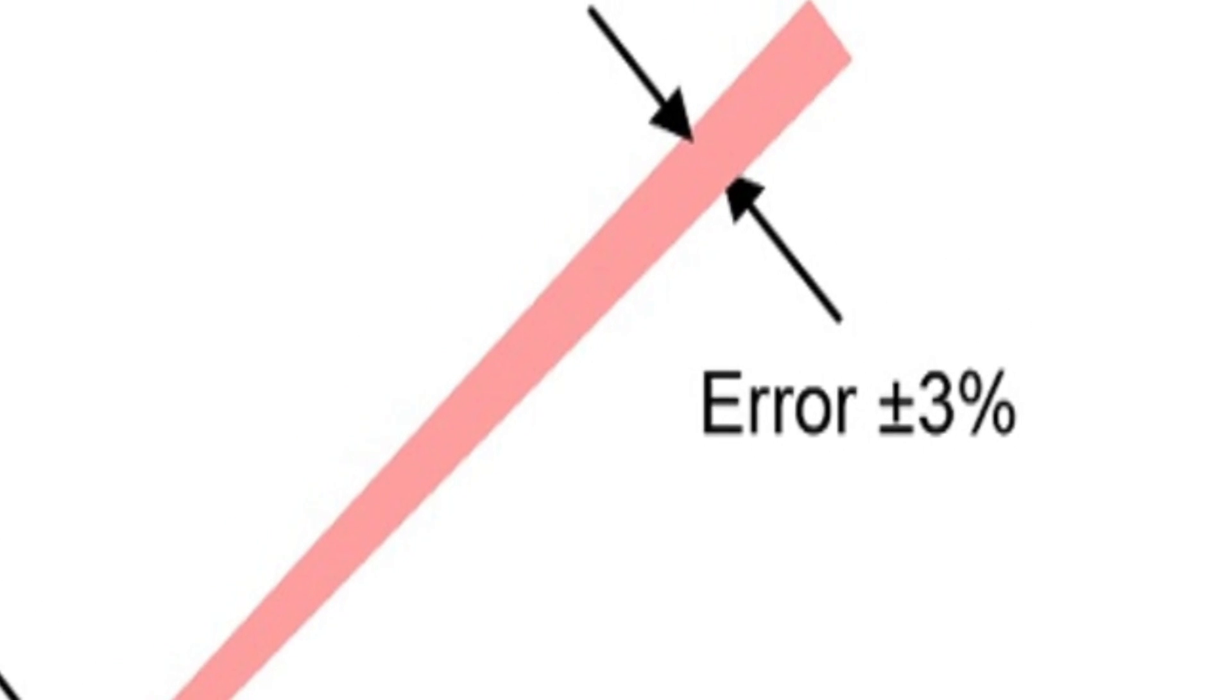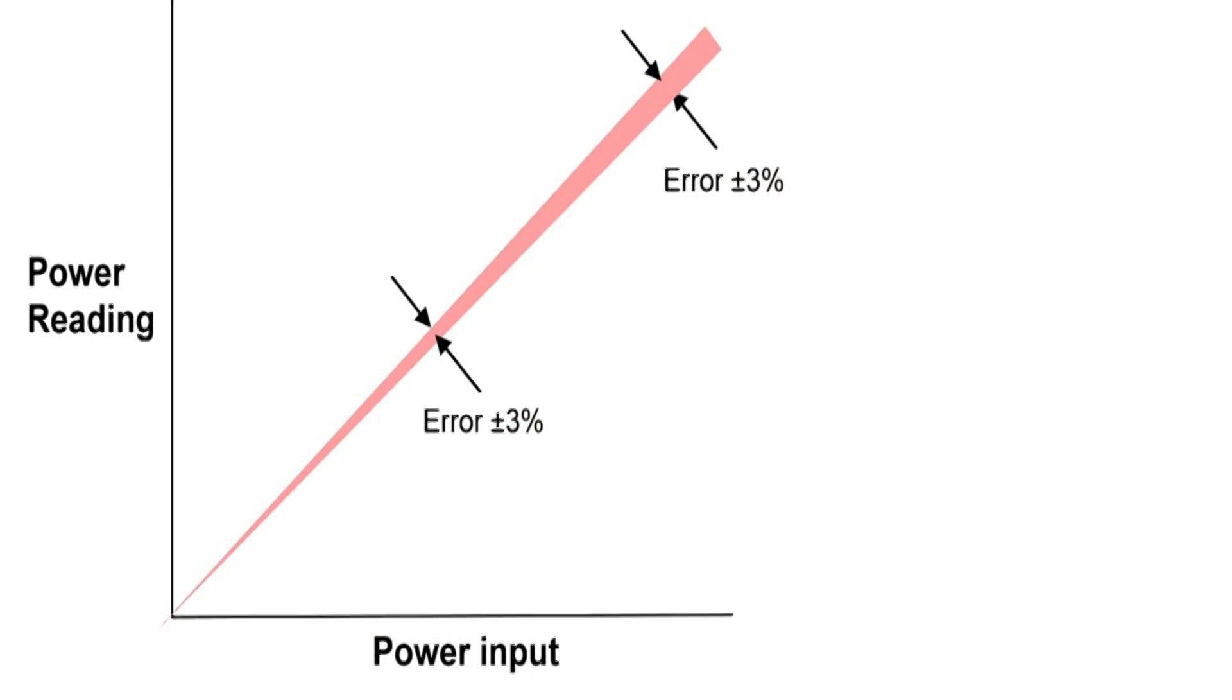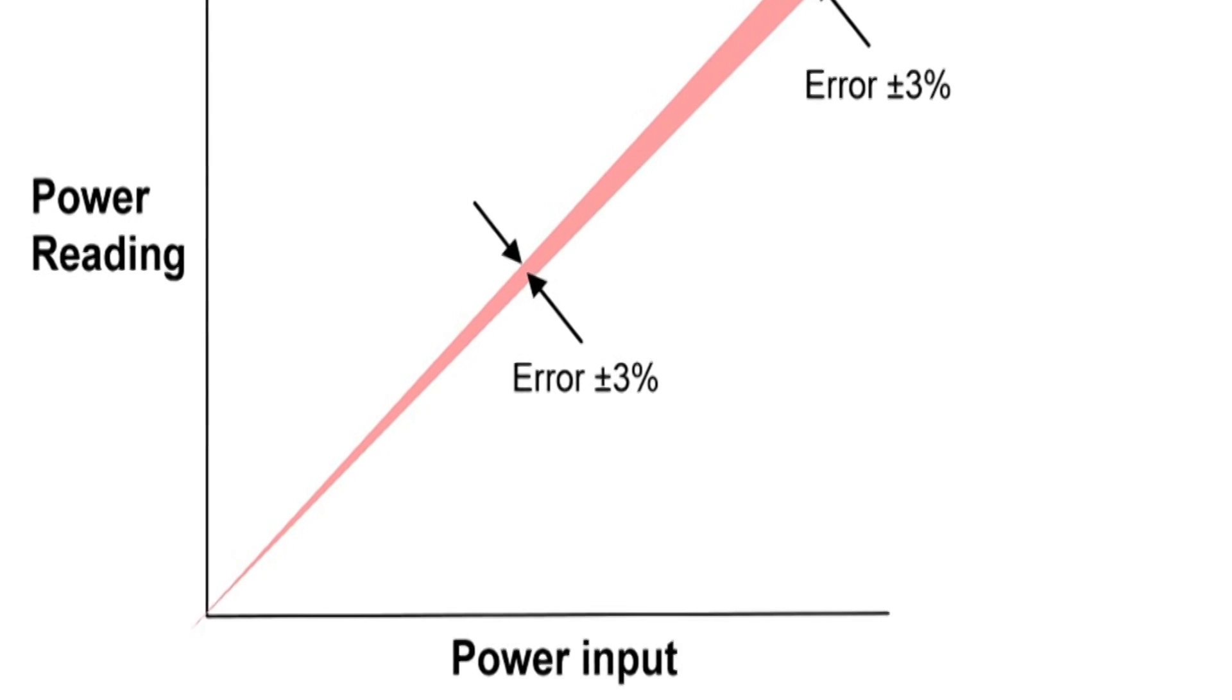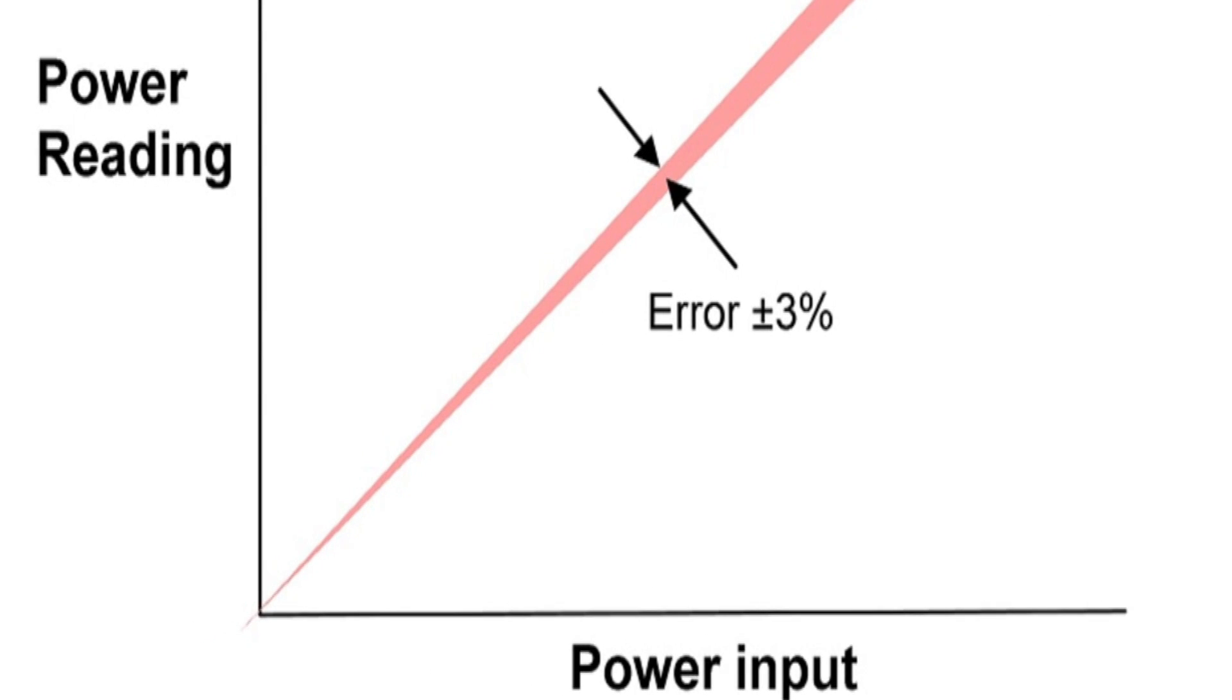Let's look at this graphically. If we're reading a high power, then we see a larger error which is still plus or minus 3% of the reading. If we're reading a lower power, we still have plus or minus 3% error in the reading, but it is a smaller value.